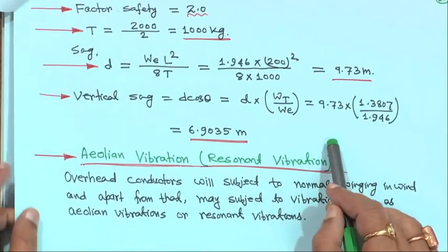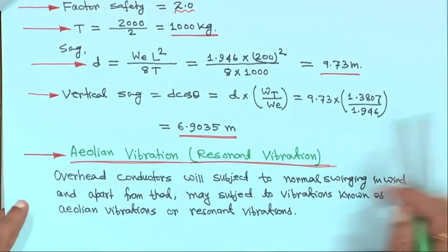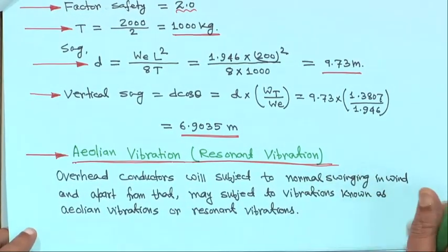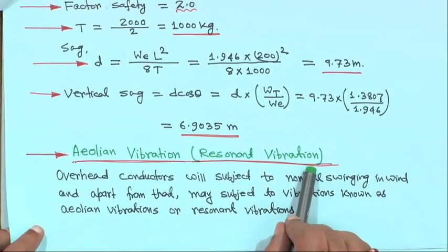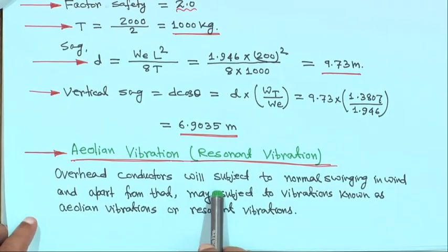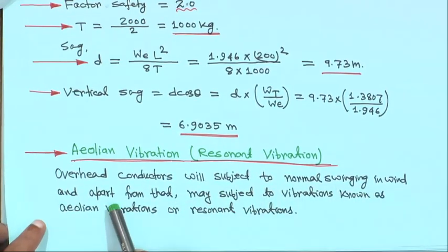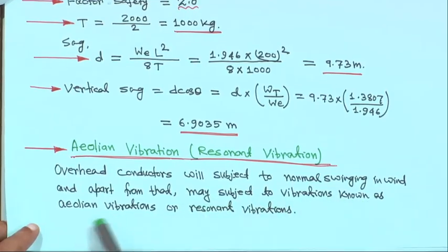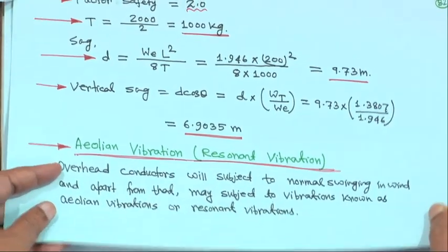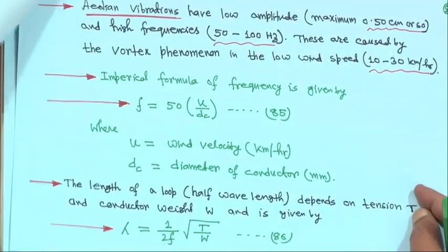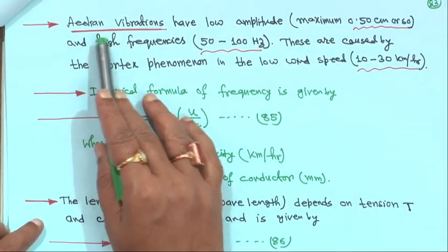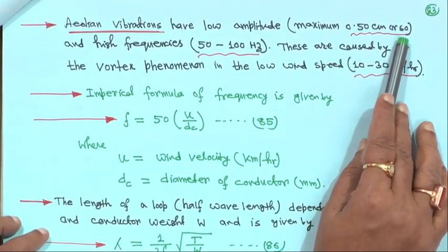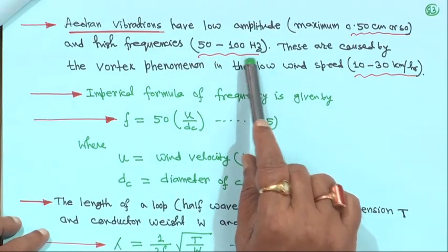With these 9 examples on sag and tension covered, before closing this chapter, a little bit on aeolian vibration or resonant vibration of the conductor. Generally overhead conductors are subject to normal swinging in wind, and apart from that may be subject to vibrations known as aeolian vibrations or resonant vibrations. These have very low amplitude — maximum maybe 0.5 centimeter — and at high frequency in between 50 to 100 hertz.